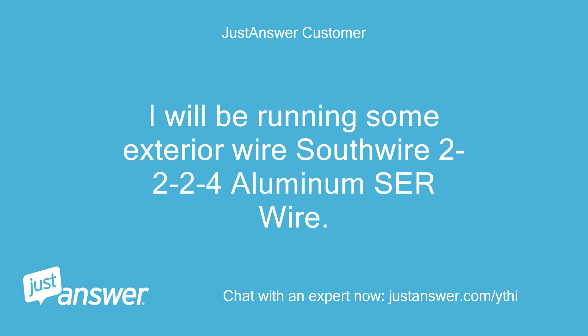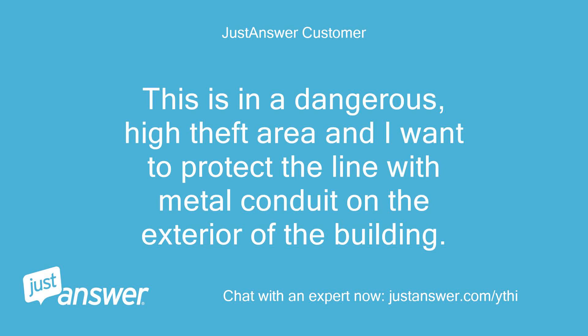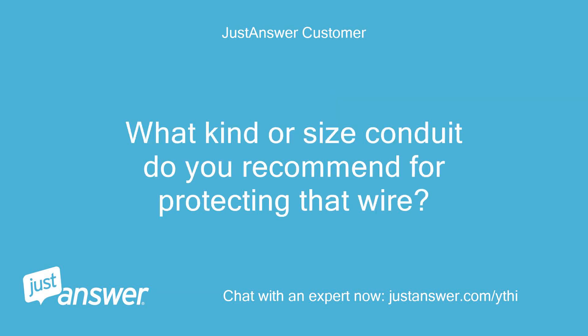I will be running some exterior wire — Southwire 2-2-2-4 aluminum SER wire — to connect the line from the top of the house to the meter. This is in a dangerous, high-theft area and I want to protect the line with metal conduit on the exterior of the building. What kind or size conduit do you recommend for protecting that wire?